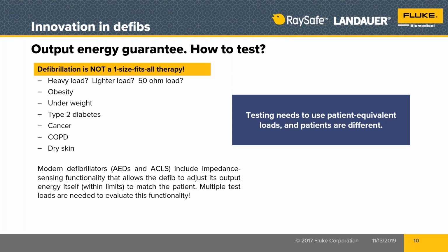But in order to test whether that functionality is working properly, you have to have more than just the standard 50 ohm test load that's required, has been required and built into defibrillator analyzers for many, many years. So what do you do about that?